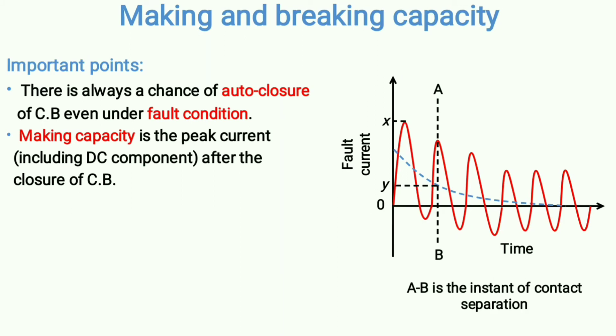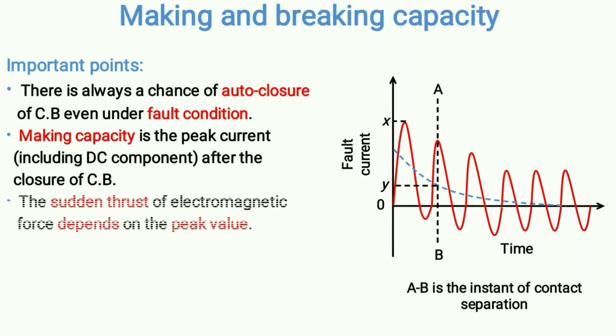After disconnecting the path, the circuit breaker waits for some time and again tries to auto-close the path, but there is a chance that the fault is not yet cleared. So auto-closing may be done even under fault conditions — that is why making capacity is important to analyze. Making capacity is the peak current after the closure of the circuit breaker, and it includes the DC component of the fault current, giving the maximum or peak value of the fault current just after closure.